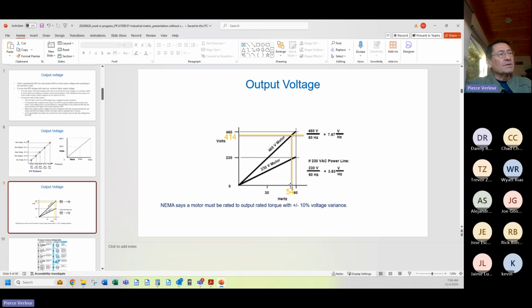From 0 to 54 hertz, we're fine, because we have enough voltage to satisfy this voltage requirement on this volts-hertz curve for the variable frequency output. Above 54 hertz, ABB is correct, if the matrix drive voltage drop is 10%, which it's not, it's less. However, I said we're going to use 10%. So above 54 hertz, we start to undervoltage the motor a little bit because of the voltage drop of the matrix drive. However, we never get less than 414 volts. Therefore, we are within the NEMA variance, even if the voltage drop across the matrix drive is 10%.